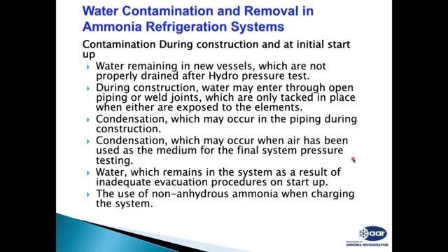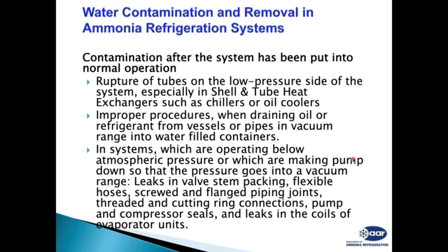The second part is the purity of ammonia. If we are not using pure ammonia, water will remain in the system. Now, the vapor pressure of water and ammonia solution is lower than that of ammonia, so water will always remain at the bottom.